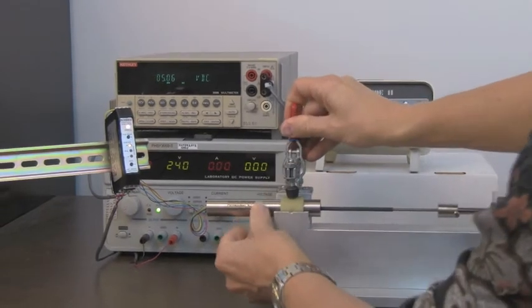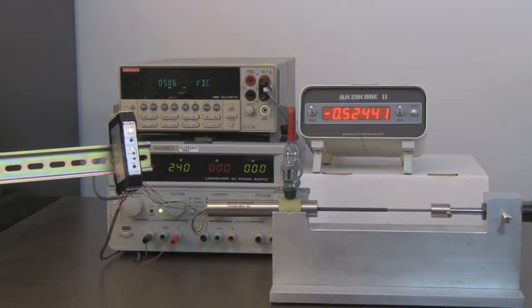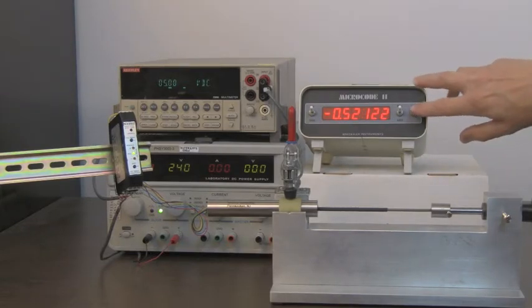Next, we adjust the digital micrometer head until the null LED indicator lamp is steadily illuminated. Being at null, we now reset the digital micrometer readout to zero.